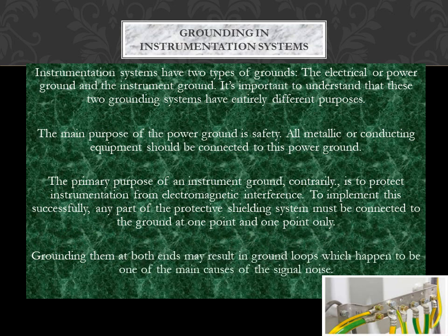Instrumentation systems have two types of grounds: the electrical or power ground, and the instrument ground. These two grounding systems have entirely different purposes. The main purpose of the power ground is safety, and all metallic or conducting equipment should be connected to it. The primary purpose of an instrument ground is to protect instrumentation from electromagnetic interference. To implement this successfully, any part of the protective shielding system must be connected to ground at one point only. Grounding at both ends may result in ground loops, which are one of the main causes of signal noise.